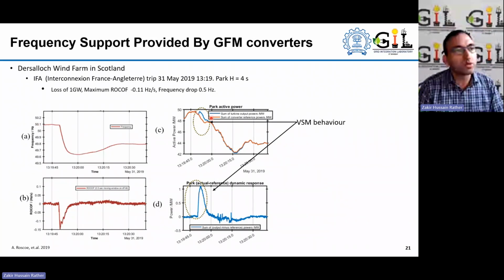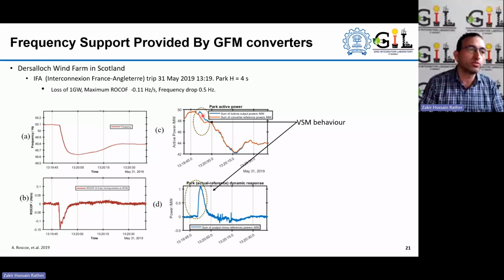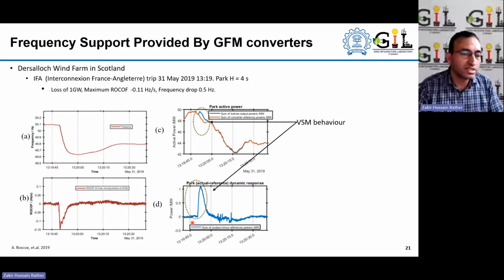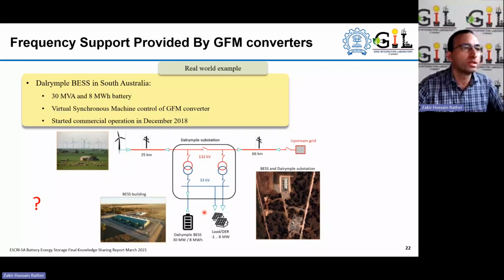And now this is the response of this wind power plant here. The blue one is actually the total response, sum of the turbine output power, and this is the sum of the converter reference. So this one is basically the power reference, and this is the actual power output. Which indicates, as you can see here, this is the additional power it is injecting in response to the frequency deviation, and the rate of change is shown here. So it is able to provide the inertial response to the grid following this large frequency deviation and rate of change in the system.